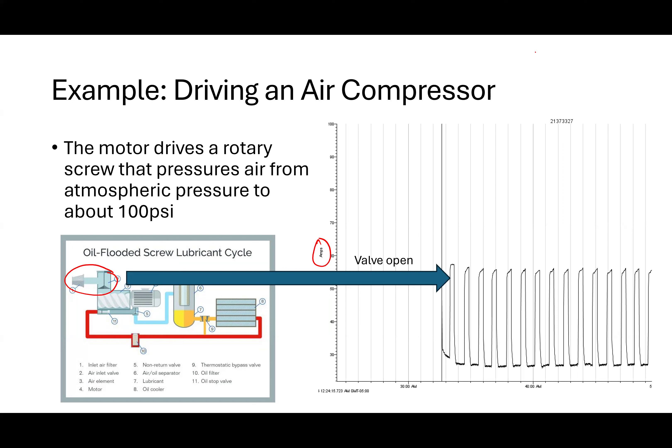Sometimes in the real world you'll see people monitoring what they call percent FLA — full load amps. On a compressor, they often say RLA, which is running load amps. What's going on at the very beginning of the graph? The current looks at least 100 amps and probably cut off on the measurement. That period is what I call the inrush — the current is very high during the inrush time for it to get itself started because it needs a lot of torque to get going. It's all related to the relationship between torque and current.